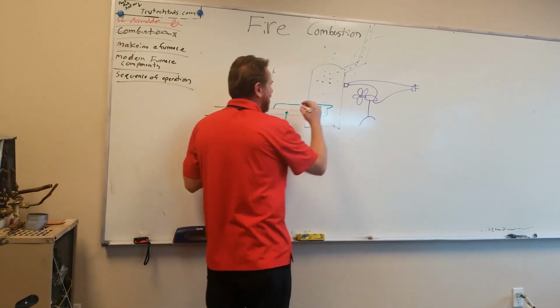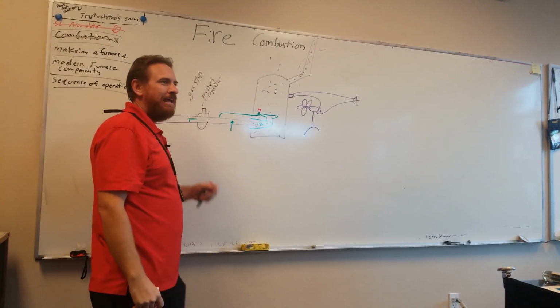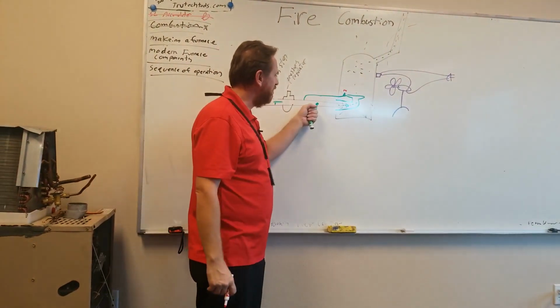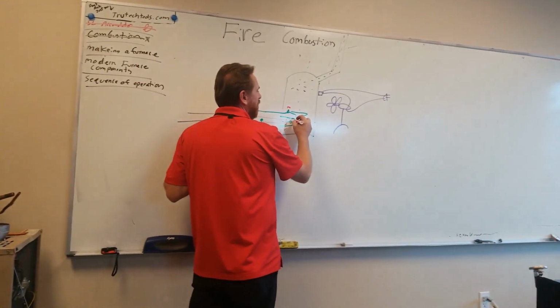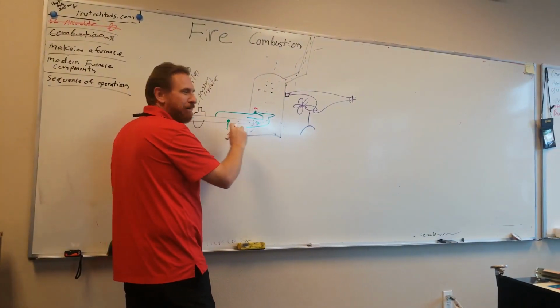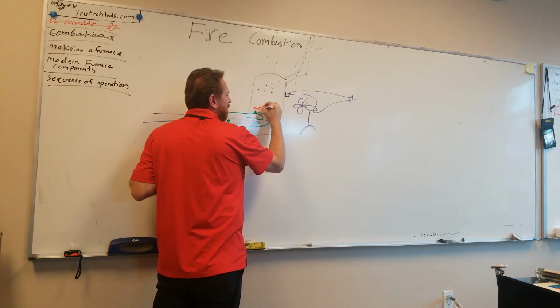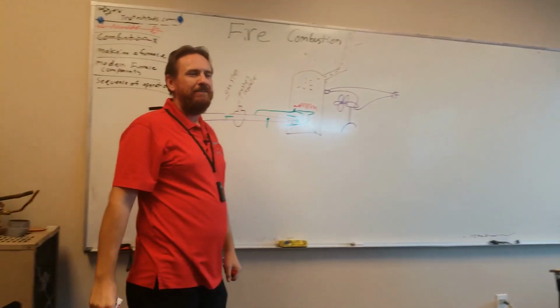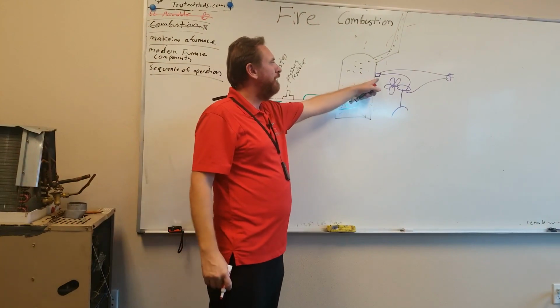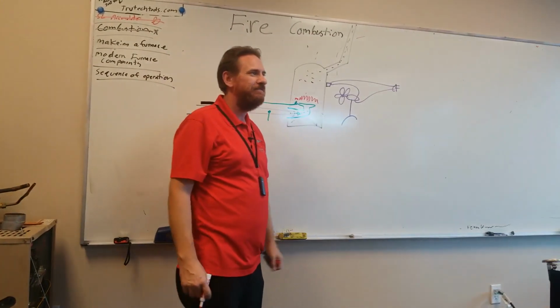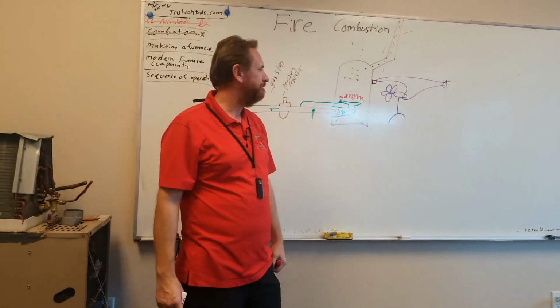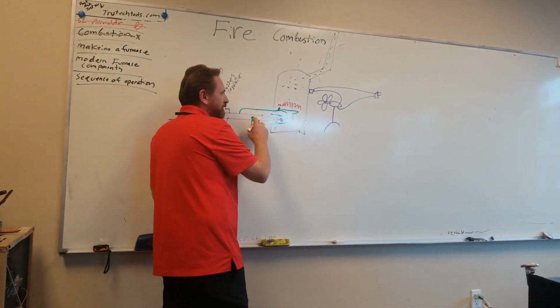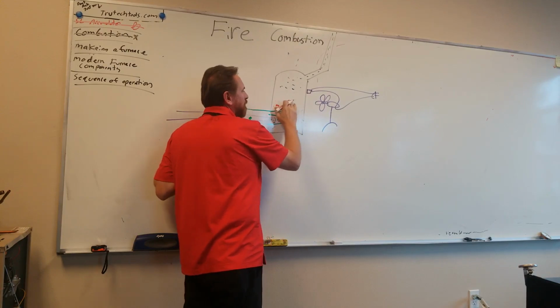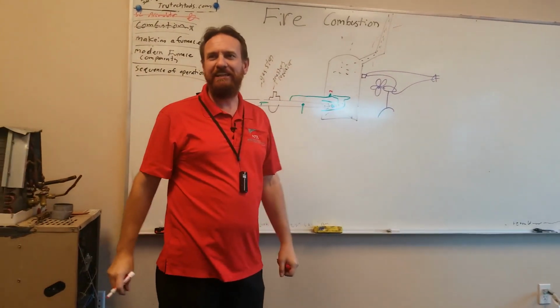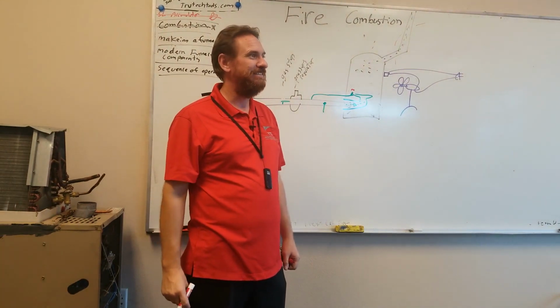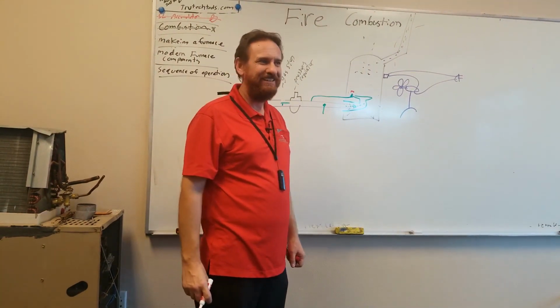So if I have my pilot burning, a little flame all the time, and it gets cool in the house, all I got to do is reach in here, turn this valve on, gas flows through the manifold, through the spud, mixing with primary air, across that pilot light and burns into a flame. Once the heat exchanger heats up, the switch brings the fan on. It's kind of nice, right? Then once I get warm, I shut this valve off. What happens to my main flame? What happens to my pilot light? Stays on. It's exactly right. Sounds good, doesn't it? Isn't that great?